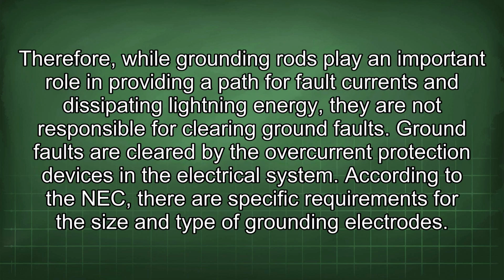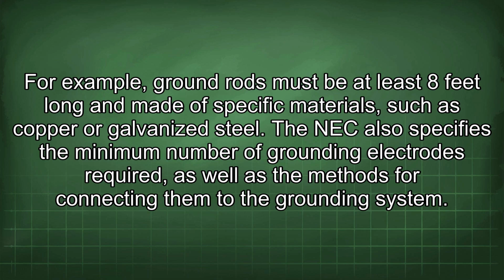Therefore, while grounding rods play an important role in providing a path for fault currents and dissipating lightning energy, they are not responsible for clearing ground faults. Ground faults are cleared by the overcurrent protection devices in the electrical system. According to the NEC, there are specific requirements for the size and type of grounding electrodes. For example, ground rods must be at least 8 feet long and made of specific materials such as copper or galvanized steel. The NEC also specifies the minimum number of grounding electrodes required, as well as the methods for connecting them to the grounding system.